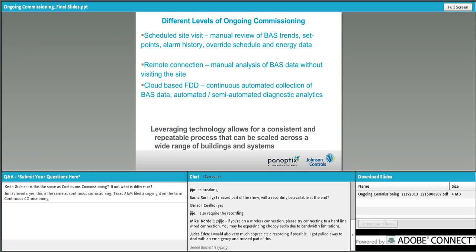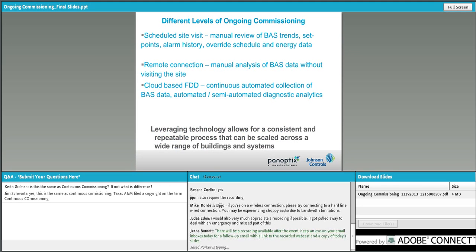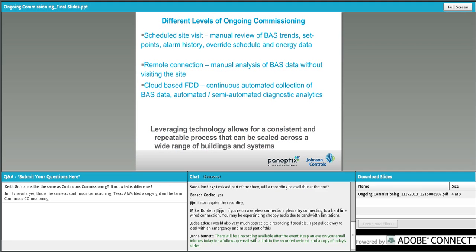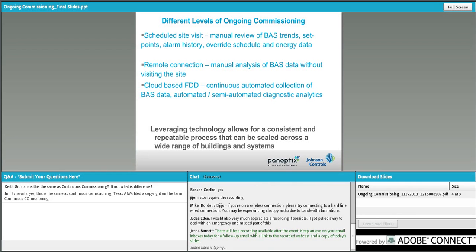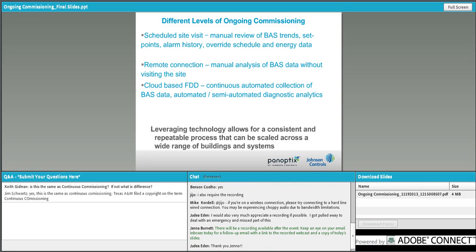So, different levels of ongoing commissioning. As Jim Bochat previously shared, there are multiple methods of implementing an ongoing commissioning program. At the most basic level, a scheduled on-site visit is made to manually review performance of building systems. This is a manual process that typically includes reviewing items such as building automation system (BAS) trend data, set points, and utility data. Interviews with the facility operations team are also generally performed. And that's a great point Jim made: get the people that manage, run, and occupy the building to help paint the picture with a broad paintbrush, to figure out what some of the challenges are and to help identify potential problem areas that may require further investigation.